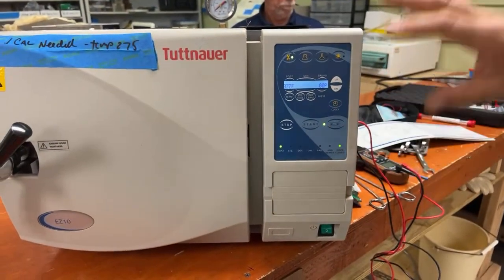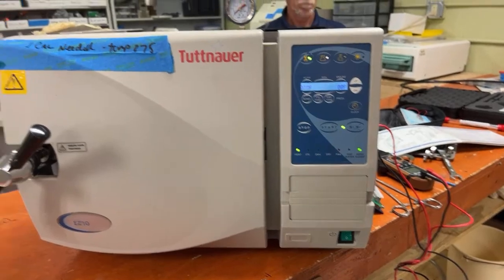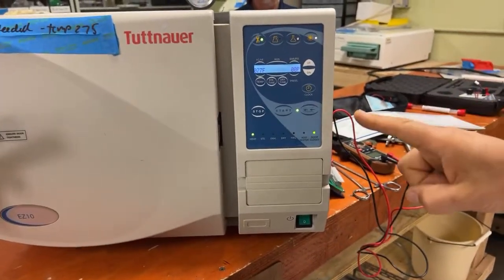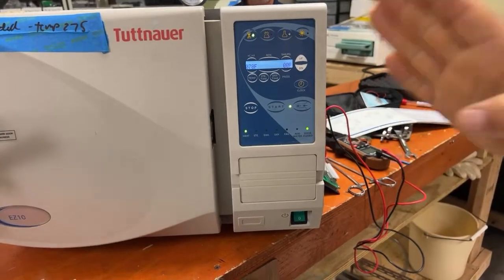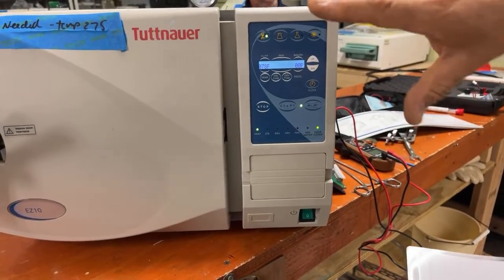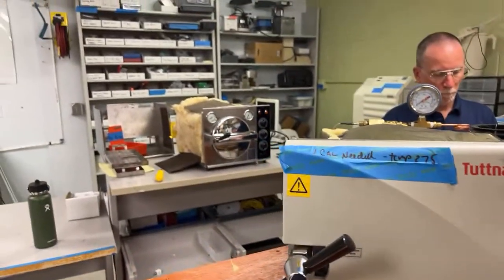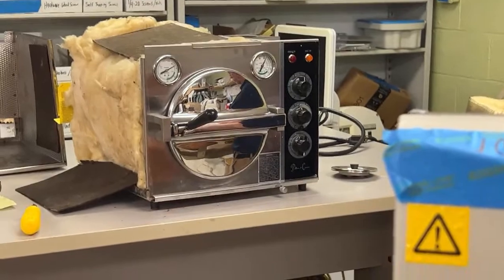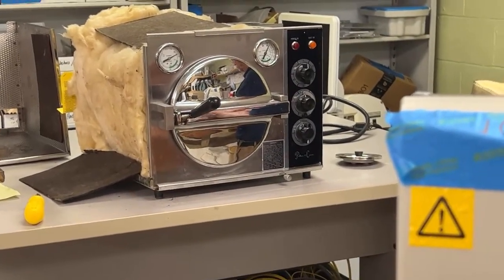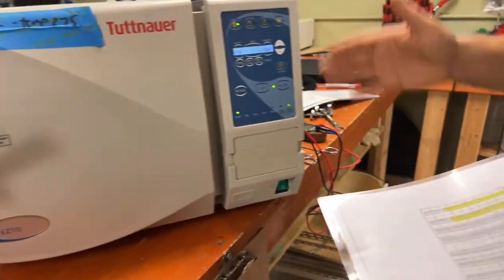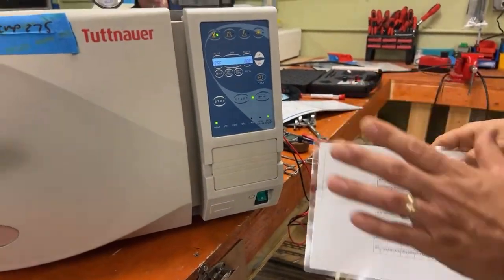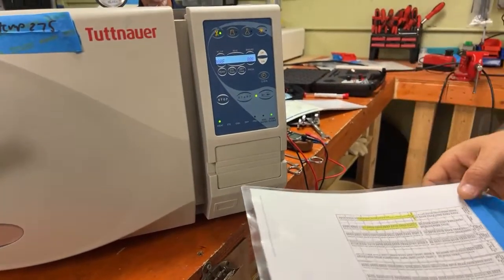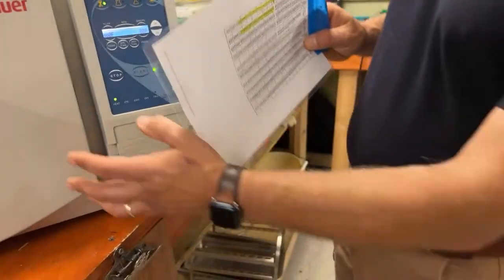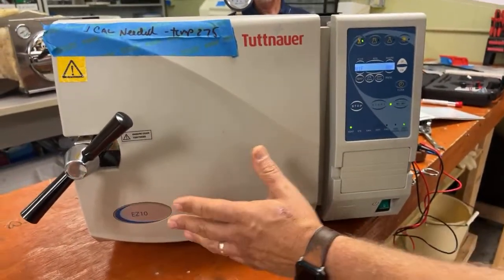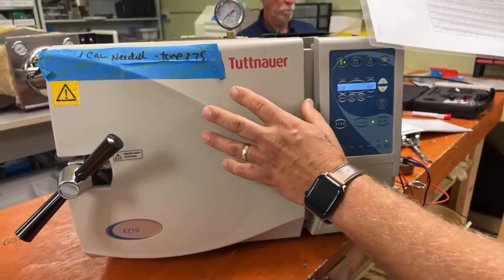This particular unit is an automatic autoclave. The difference between an automatic autoclave and a manual autoclave is that an automatic autoclave always has a button on it called start. If your autoclave has a start button, you have an automatic autoclave. Now, if you have an autoclave with a knob that you turn around in circles and you go from fill to sterilize to vent to off, that is a manual autoclave. So keep in mind, this is how these devices are classified, and that's how you know the type of unit you have. The other thing about the Tuttnauers that is special for them is they have what's called closed door drying.